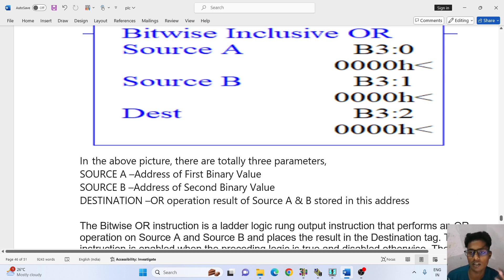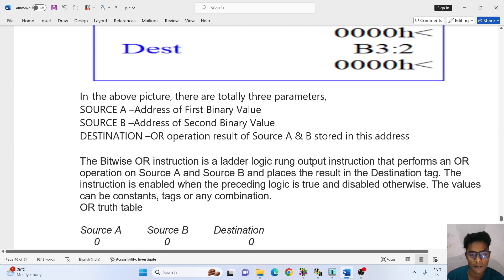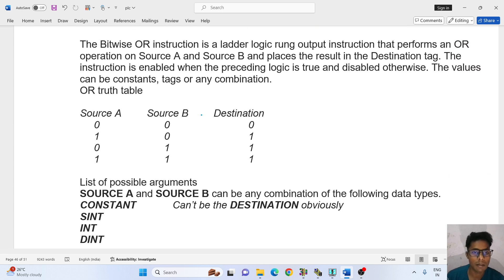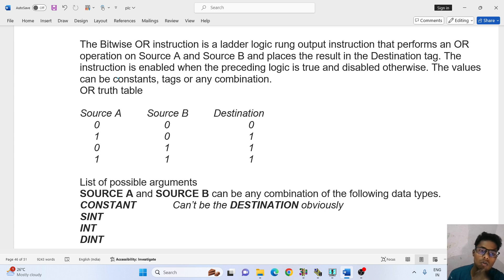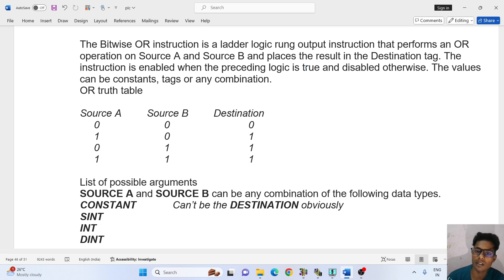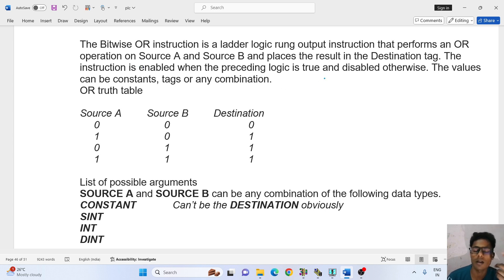So engineers, I hope you understand about it. The bitwise OR instruction is a ladder logic rung output instruction that performs an OR operation on source A and source B, and places the result in the destination tag. The instruction is enabled when the preceding logic is true, and disabled otherwise. If source A is true, your output is true.